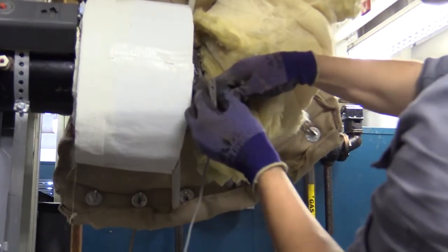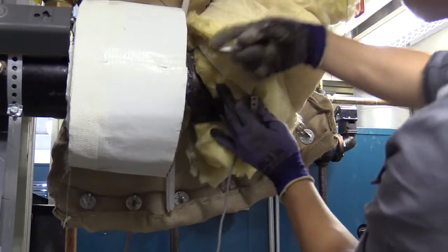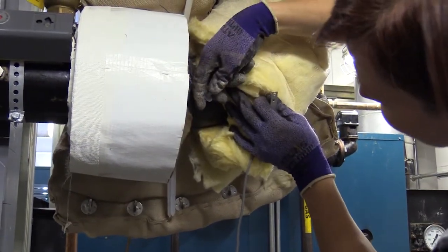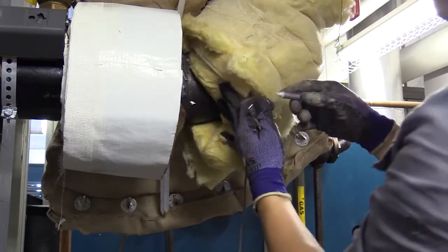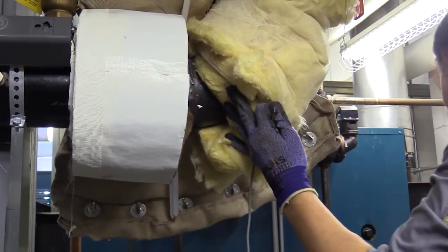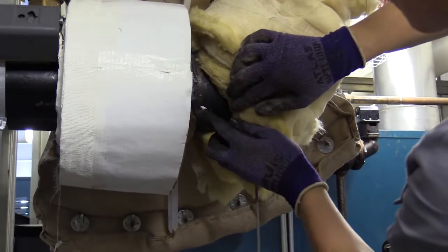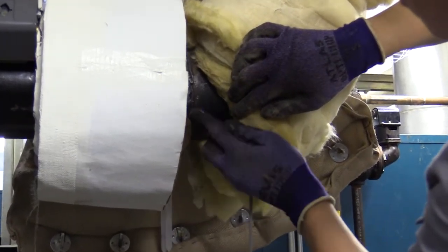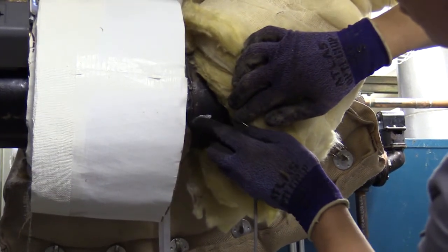And you'll apply a small amount of thermal paste to the pipe. This is also known as a thermal compound or thermal grease, and this helps with the thermal transfer to the sensor. You'll apply a thin, even layer, just enough to help the sensor make contact with the pipe.